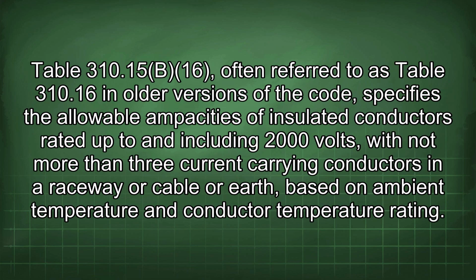Table 310.15(B)(16), often referred to as Table 310.16 in older versions of the code, specifies the allowable ampacities of insulated conductors rated up to and including 2000 volts, with not more than 3 current-carrying conductors in a raceway or cable or earth, based on ambient temperature and conductor temperature rating.